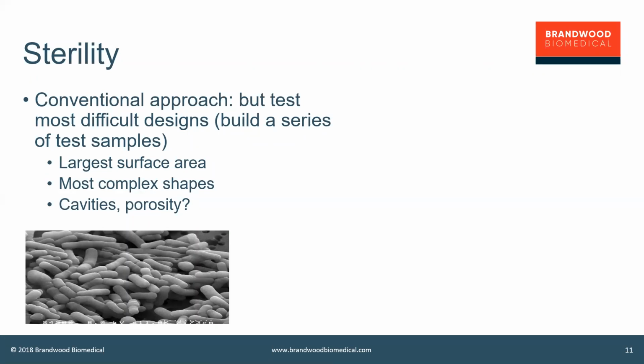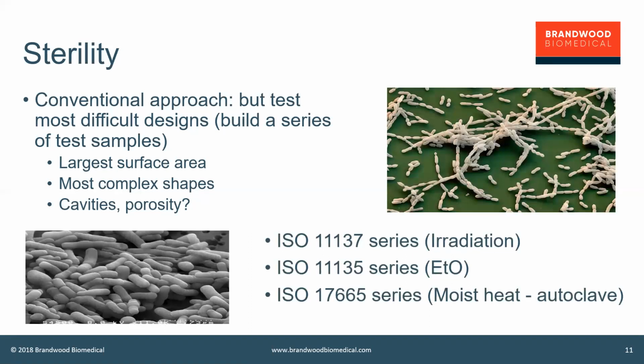The way to do it would be to build a series of devices which are effectively worst case devices, run those through your production process, package them as they would normally be, and then run them through a sterilization validation. I'm not going to talk about how you do sterilization validations. That's not what we're really here to do today in the general sense. But there are well-defined ways of validating sterility, all written down in ISO standards.